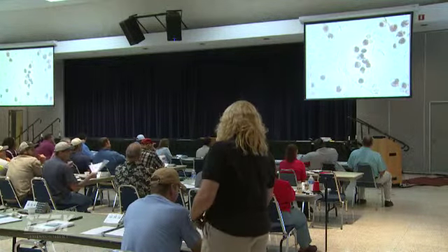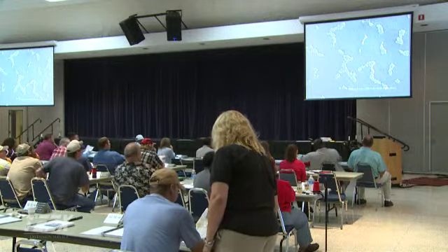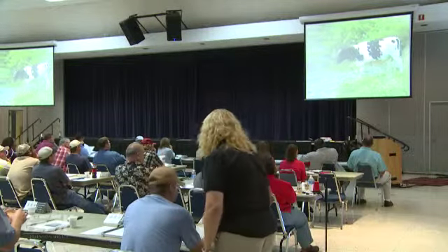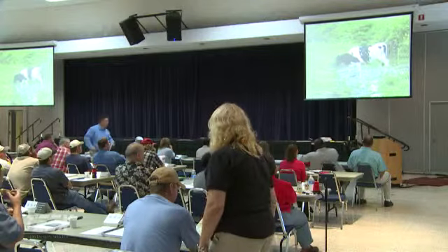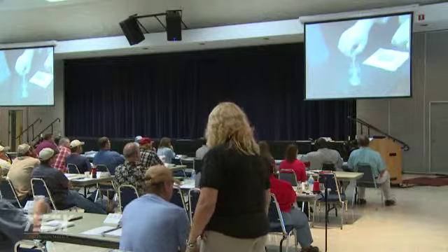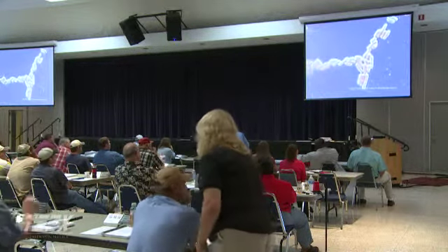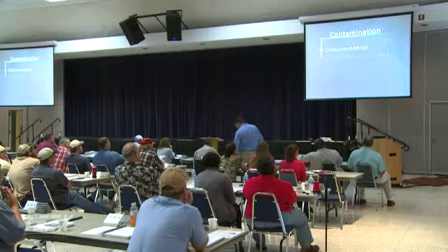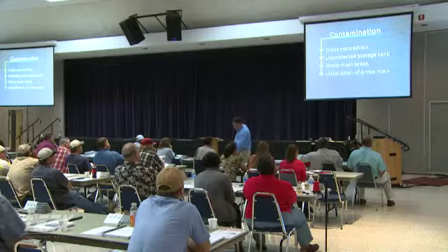When total coliform bacteria are detected, the system is then checked for Escherichia coli, or E. coli, normally associated with fecal contamination, since these bacteria can be a sign that the system could also be compromised by disease-causing organisms. This is why, when sampling finds a positive total coliform, it is tested for E. coli, a bacterium that should not be found in the finished water of the distribution system. Contamination in the distribution system can occur through a cross-connection, an unprotected storage tank, a water main break, or the installation of a new main.